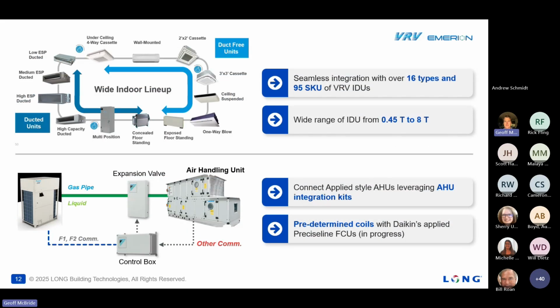Focus on the bottom portion of this screen. The upper portion shows the types of fan coils that pair with both water-cooled and air-cooled VRV systems. Daikin has a big lineup of both ducted and ductless. But I want to point out that we're now seeing a lot more VRV air-cooled condensing units paired with third-party air handling units. So this is more of a ventilation solution for you. If you've got a project that is getting rid of gas and needs to go all electric, this is a good opportunity to look at these types of products that we have.